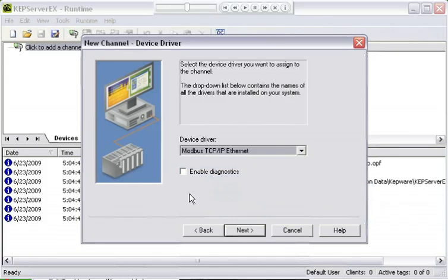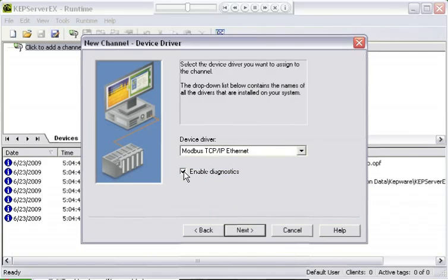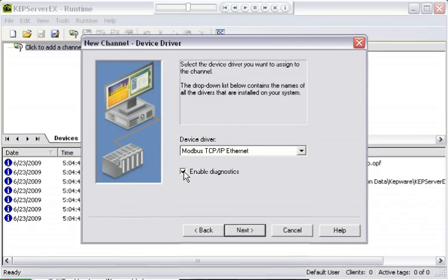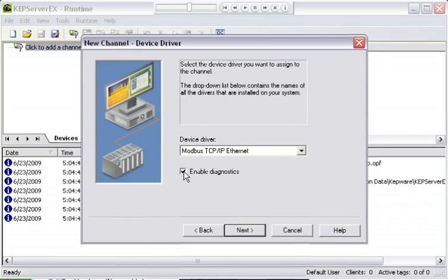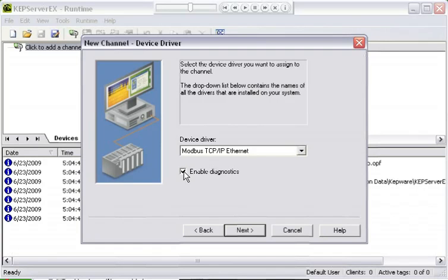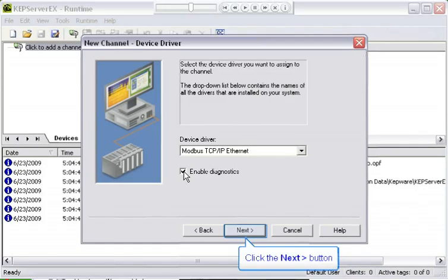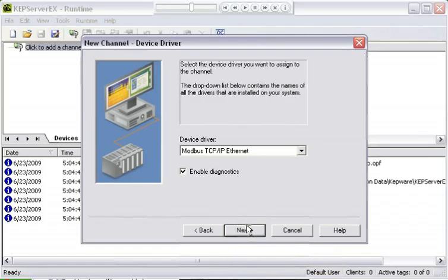The next thing I'm going to do is enable channel diagnostics. I do this so that I can diagnose any communications problems. The way the diagnostics works, and we'll go over this in detail in some other lesson, is it captures the communications between the channel and the device or devices, and it does that outside of the server. It does that at the com library for serial drivers or at the socket manager for Ethernet drivers. Now that I've selected my properties, I'm going to click next.